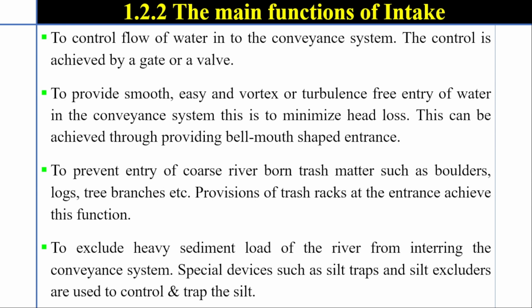1.2.2 The main functions of intake. To control flow of water into the conveyance system, the control is achieved by a gate or a valve. To provide smooth, easy, and vortex or turbulence-free entry of water into the conveyance system, to minimize head loss. This can be achieved by providing a bell-mouth-shaped entrance. To prevent entry of coarse, river-borne trash matter such as boulders, logs, and tree branches, an extra provision of a trash rack at the entrance achieves this function.